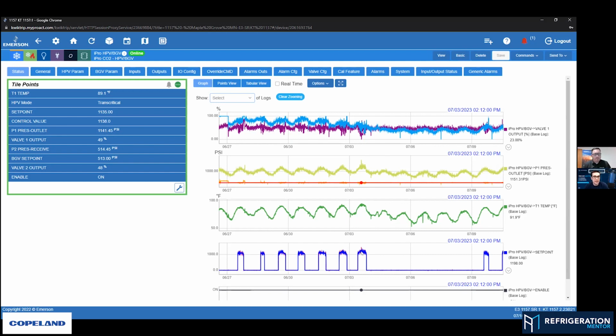It's a little complicated. Another thing that I want to point out on the screen, anyone listening, is the valve percentages. If you haven't worked with electronic valves before, you've got to just start learning and watching a system when it's running normally, what that valve percentage is. And that's going to be key, because if we were looking at this screen and the valve output one, which I'm assuming is high pressure valve one, if that was 100% open, that would be concerning for you. Or if it was 100% closed, it would be concerning as well, because the system would probably be off. Yeah, exactly. And that's for the E3, that's really the onboard graphics now in the screen.